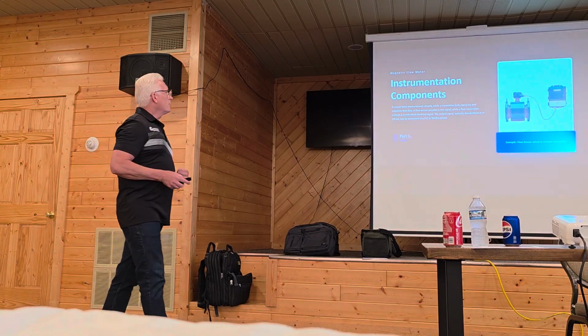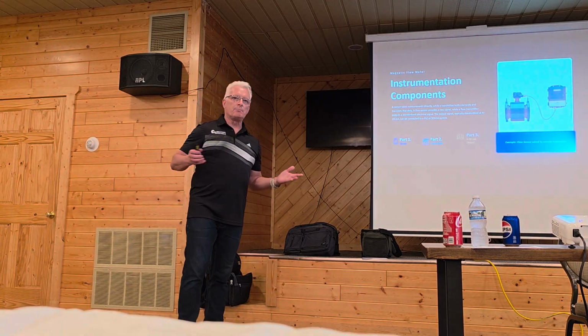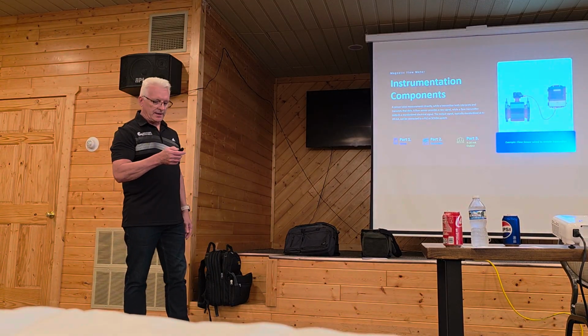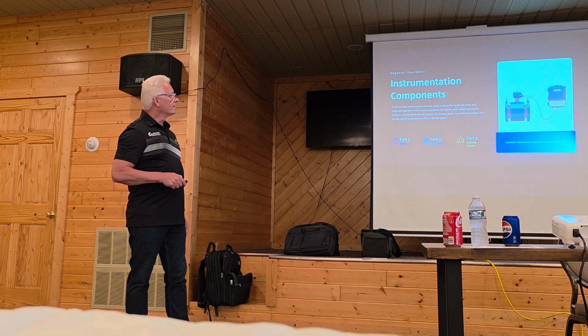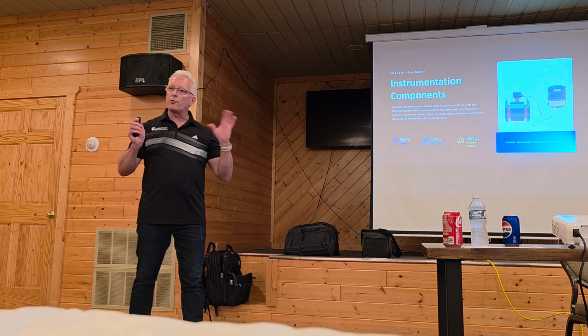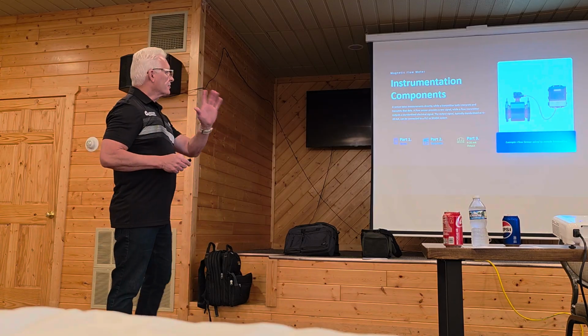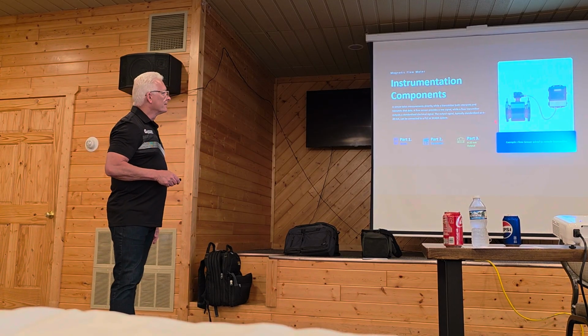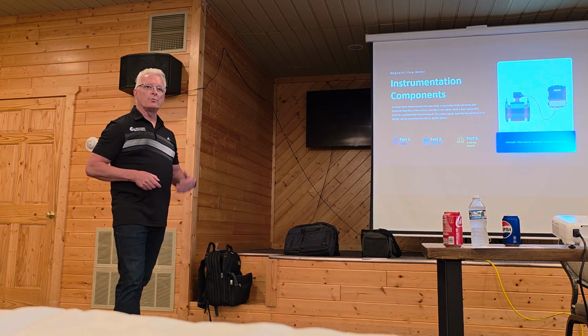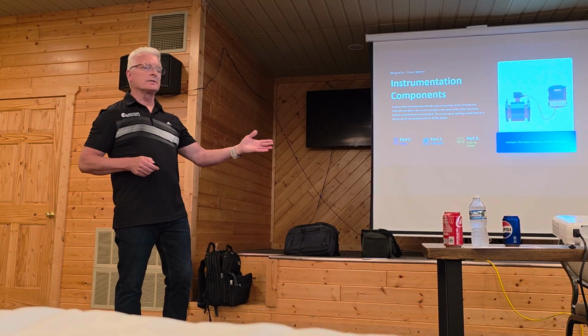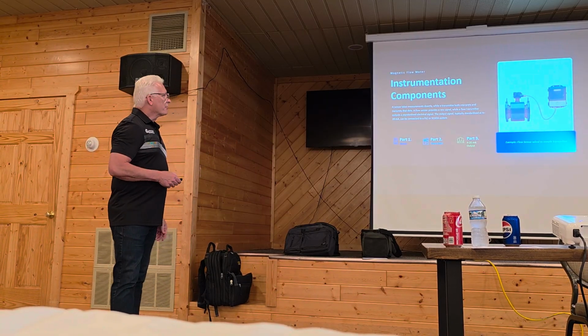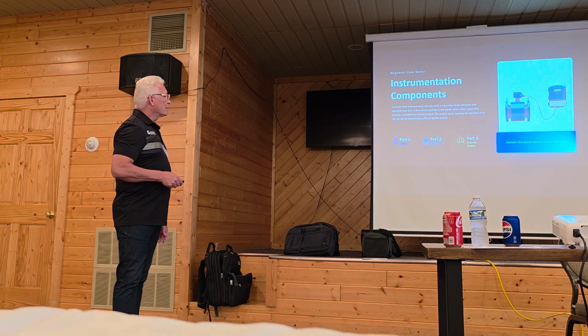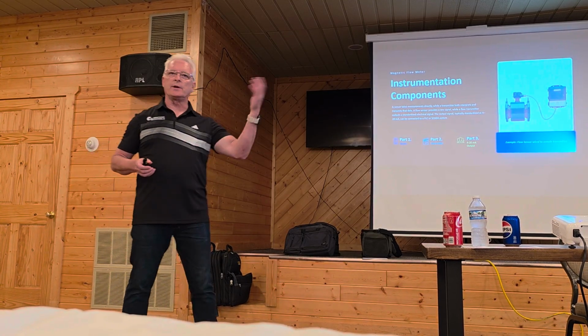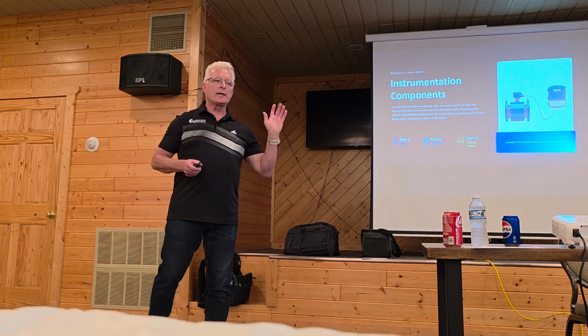Magnetic flow meters, the basic components: usually you'll have a transmitter, and that's usually where the readout is. That's kind of the brains. Then you have the sensor, which is actually in the line, reading the pH or the flow or whatever it is. So you have three parts: the sensor, the transmitter, and then the 4 to 20 out, which goes from the transmitter over to your system so that it can make decisions based on that. And that's what I'm talking about.